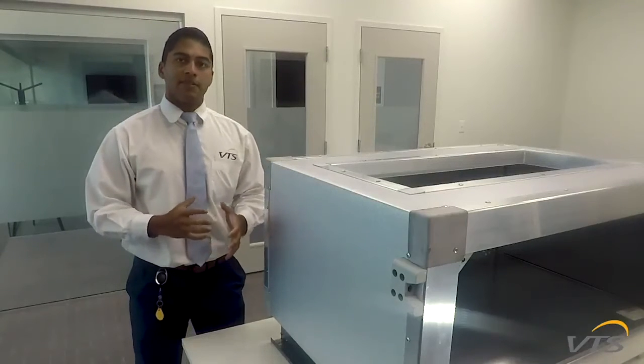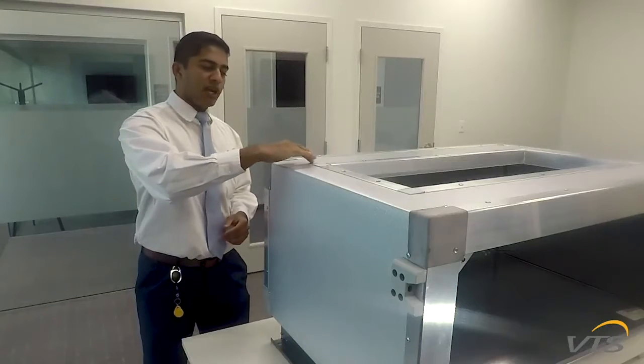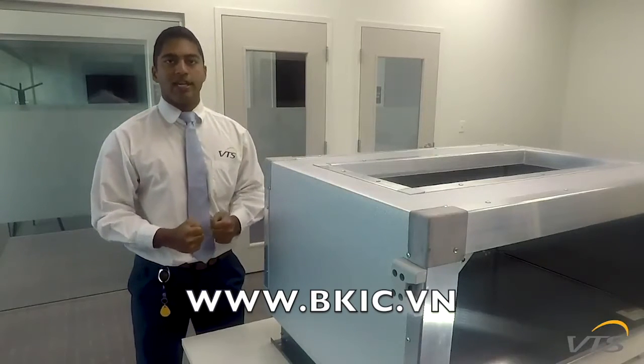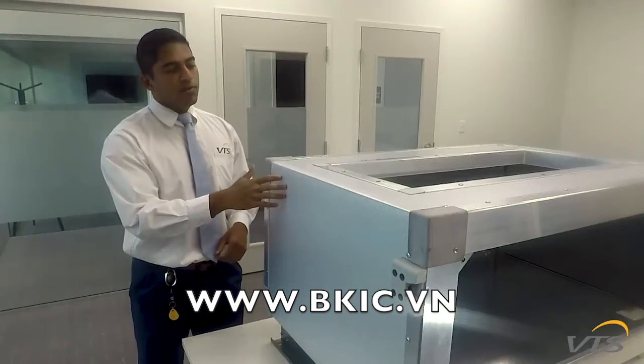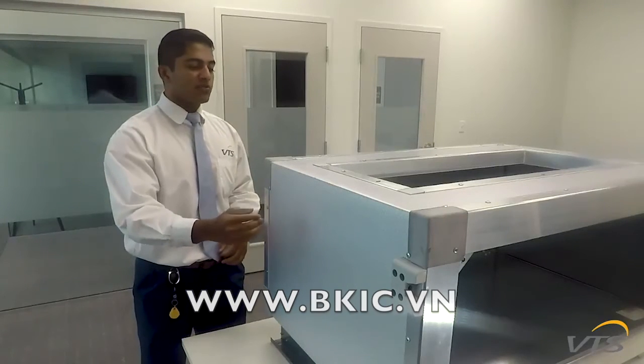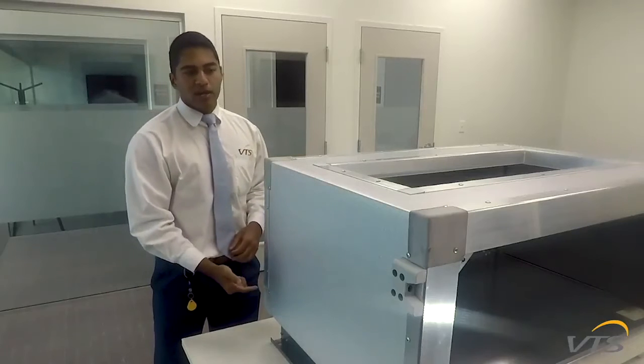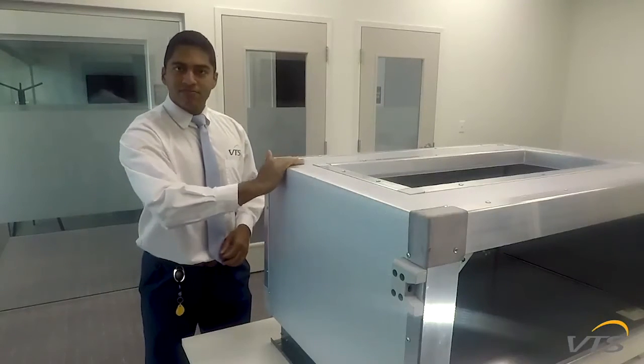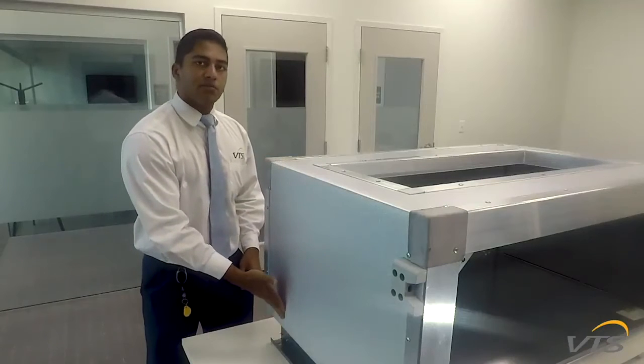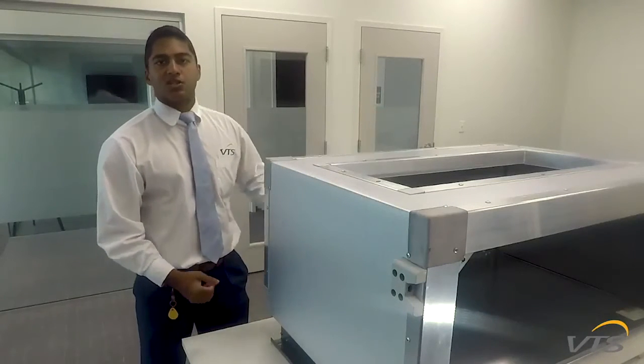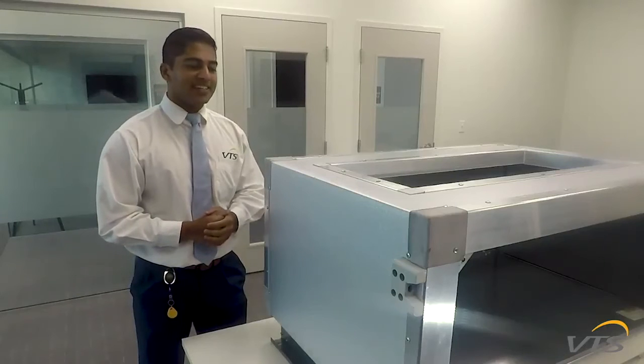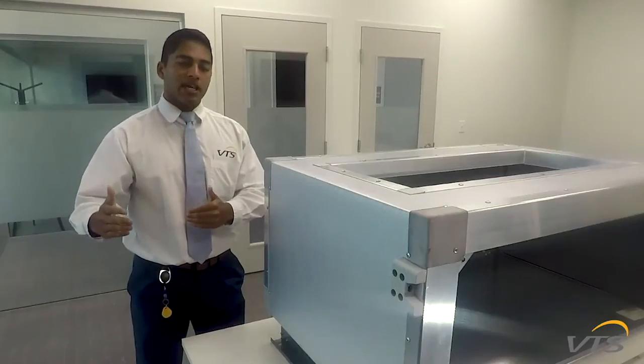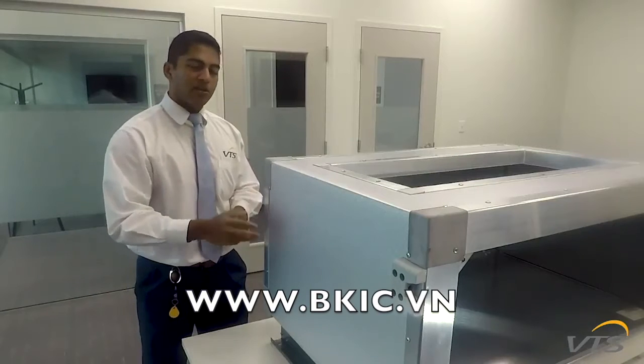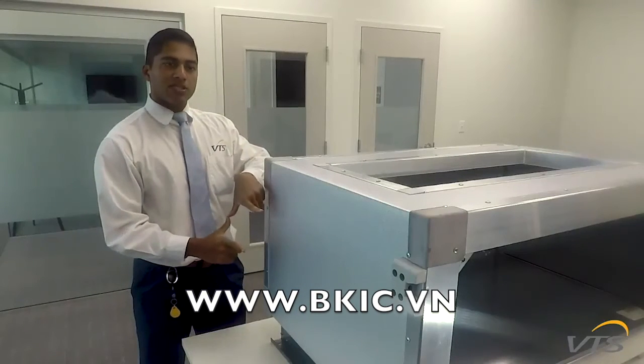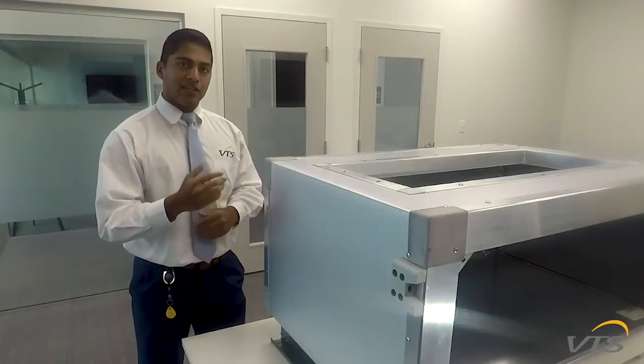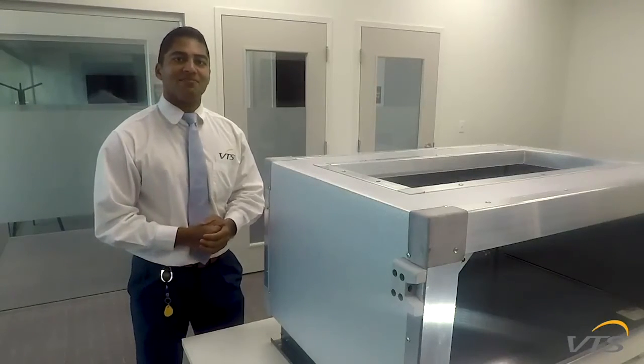To minimize any air leakage or potential for air leakage, we do a wraparound casing design with an internal framework. So in our smaller box sizes, from the AVS 8 to the AVS 40, we do a single piece wraparound construction. This means we have no open seam here, same at the bottom. We only have 2 seams where the access doors are fastened onto the unit casing. And as we go up in size, we go from the single C-shaped panel to 2 L panels that form a C, with our largest units having 3 panels combine to form that C shape.